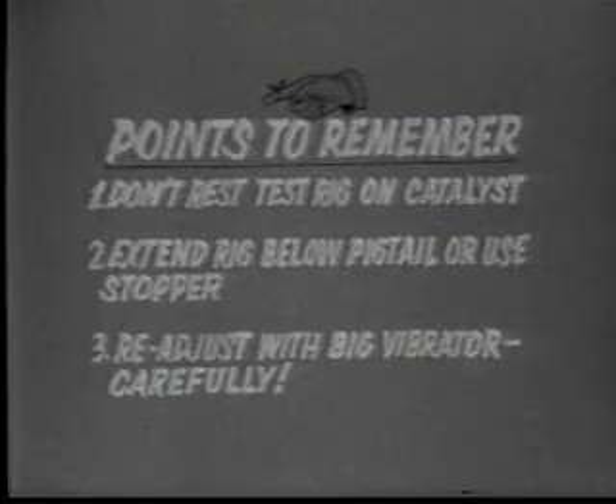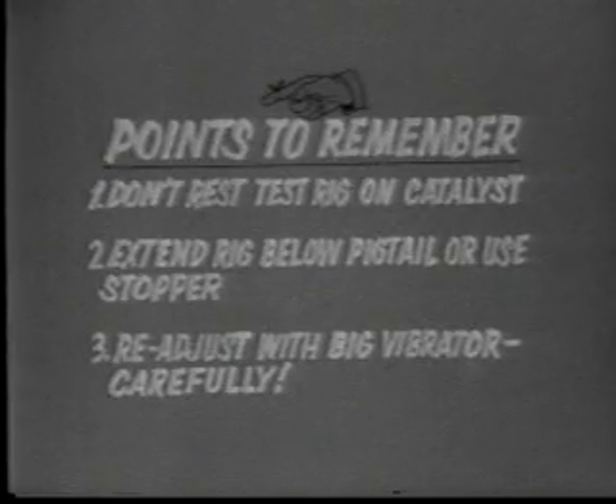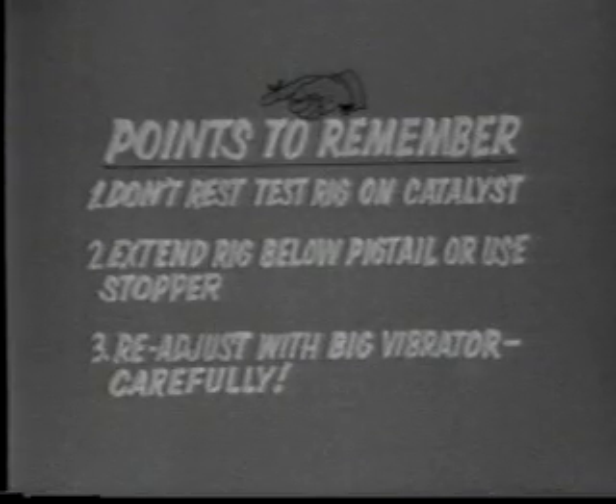The catalyst. If you do, you may get an erroneous reading. 2. If the catalyst is so high in the tube that you cannot get the DP test rig below the pigtail, use a stopper to plug off the pigtail opening.